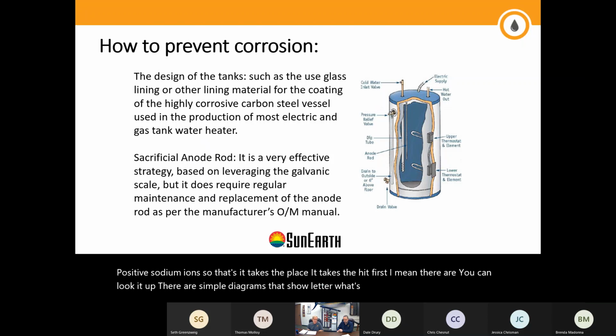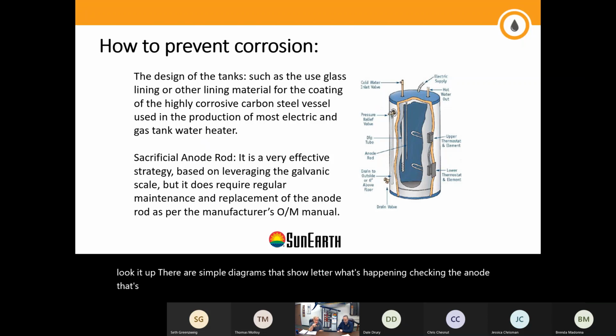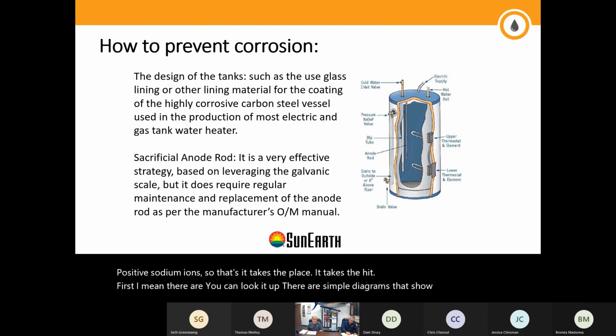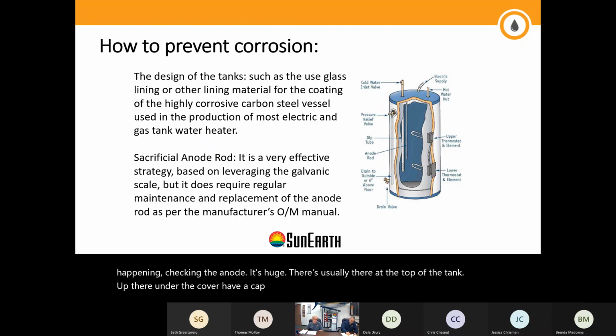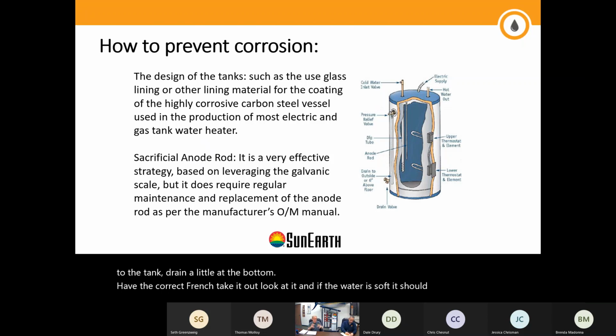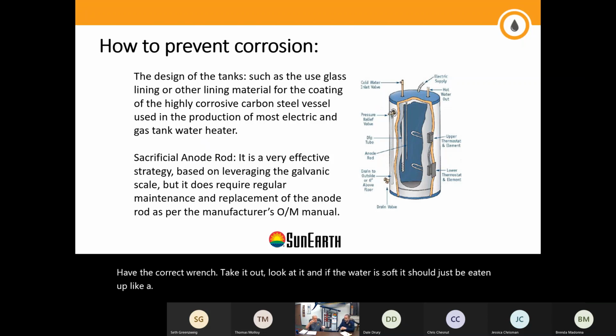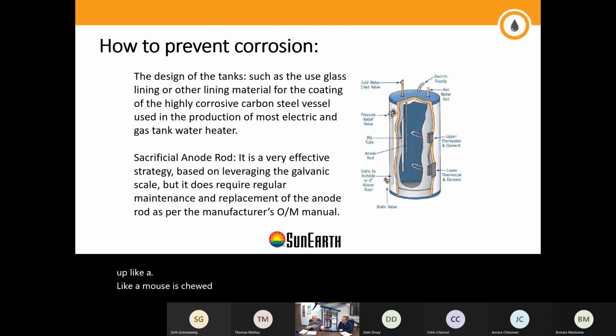Checking the anode: usually they're at the top of the tank. They're under the cover, with a cap. Some are easier to take out. You just turn the water off to the tank, drain a little at the bottom, have the correct wrench, take it out, look at it. If the water is soft, it should just be eaten up, like a mouse has chewed it up, like you see sometimes a piece of vegetable chewed up.